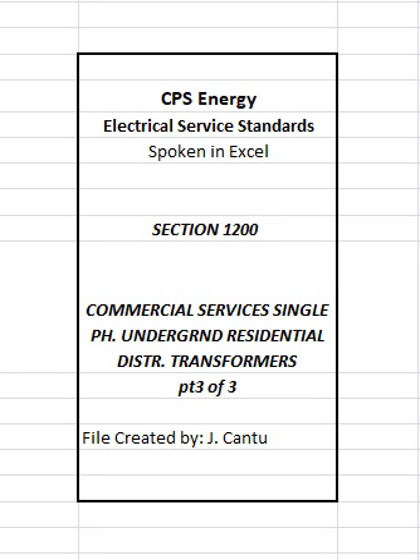3. Where the subsoil conditions are questionable, CPS Energy shall require the customer to provide a Proctor density test at their expense to establish whether the slab shall be installed on piers. A 90% Proctor test is necessary to eliminate the need for piers. 4. Customer shall furnish and install two 5/8-inch x 8-foot copper or copper-clad ground rods in the slab opening, as specified in CPS Energy slab detail. CPS Energy will provide and install all necessary ground rod connectors.